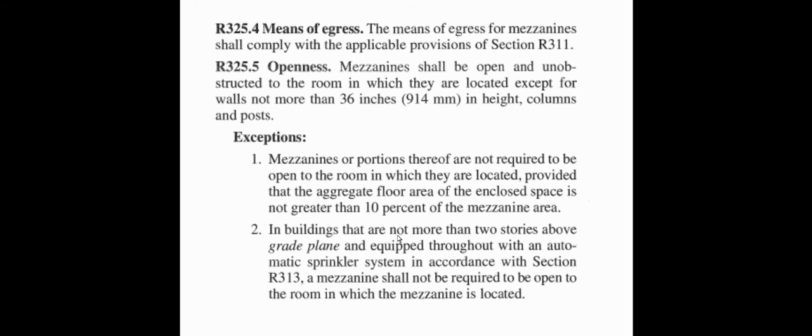In buildings that are not more than 2 stories above the grade plane equipped throughout with an automatic sprinkler system in accordance with section 313, a mezzanine should not be required to be open. So once you sprinkle it, I don't have to open it no more.